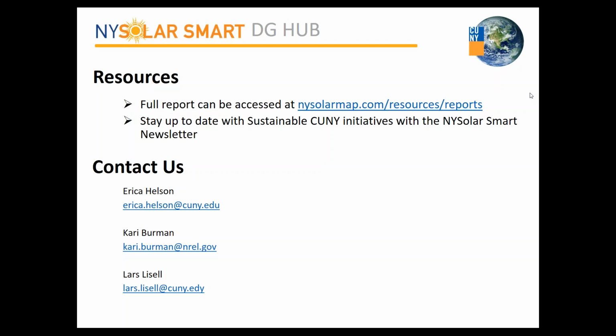You could have a manual switch. You could also have a manual switch, but then if the grid dropped, you'd have to physically walk out there, throw the switch, and it would operate the same way. Right. So in a similar vein of questions, in your research, did you see any systems that didn't actually have critical loads isolated on a subpanel, where it was done more by switching off the non-critical loads to isolate the loads, instead of going through the rewiring to put in a critical load subpanel? Yeah, absolutely.